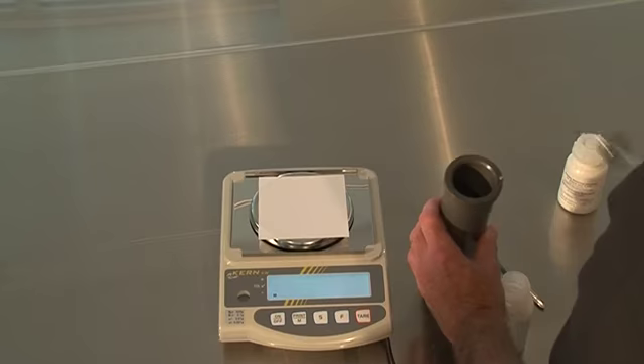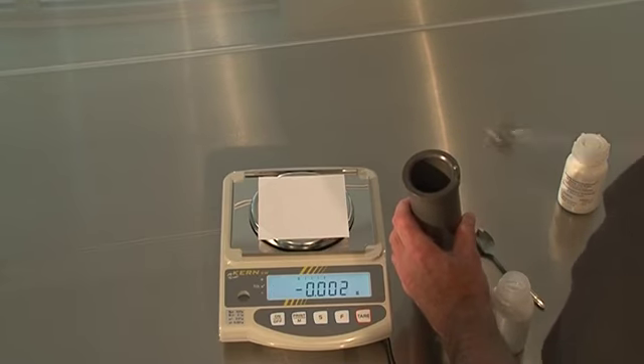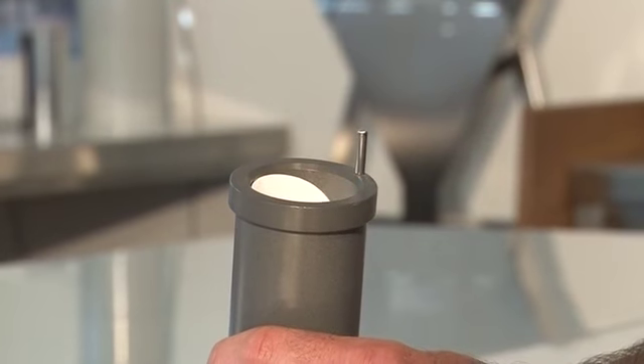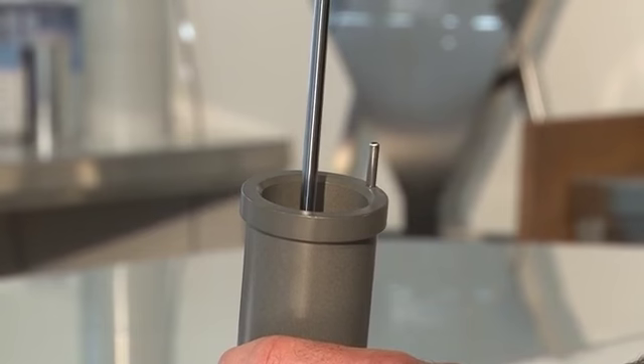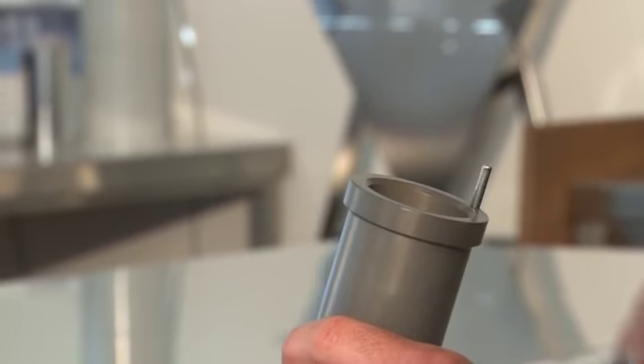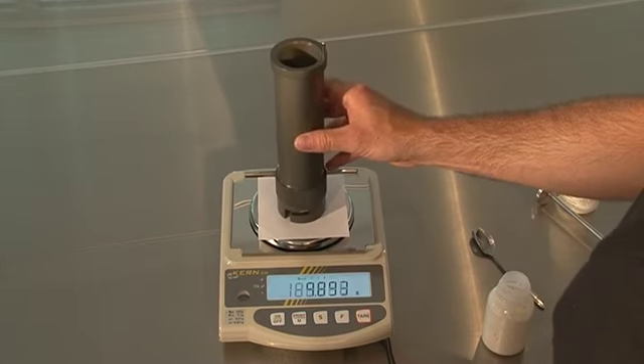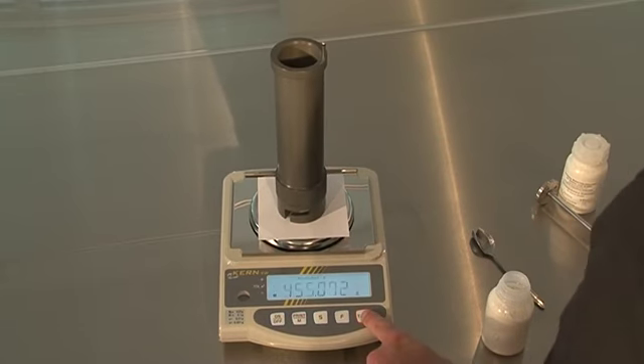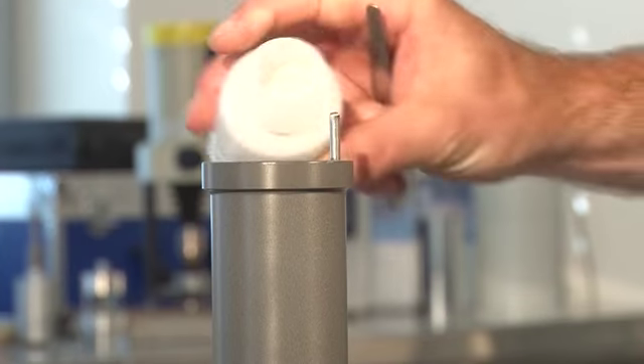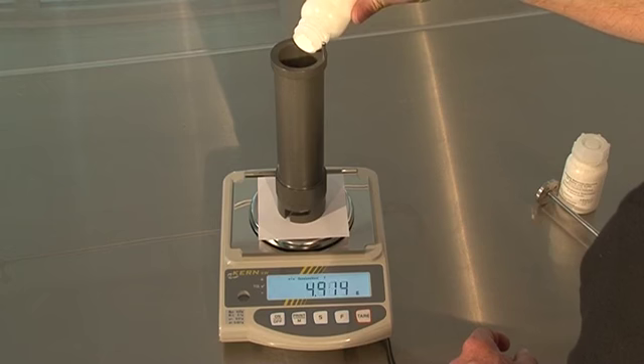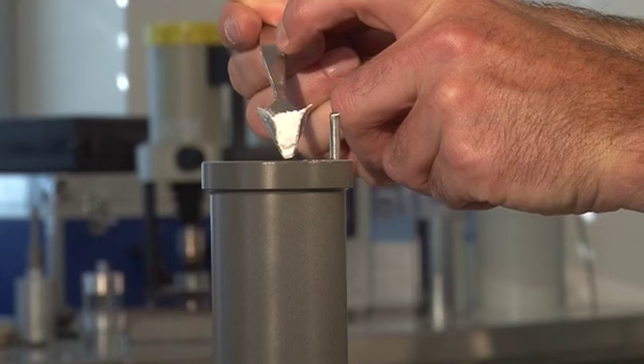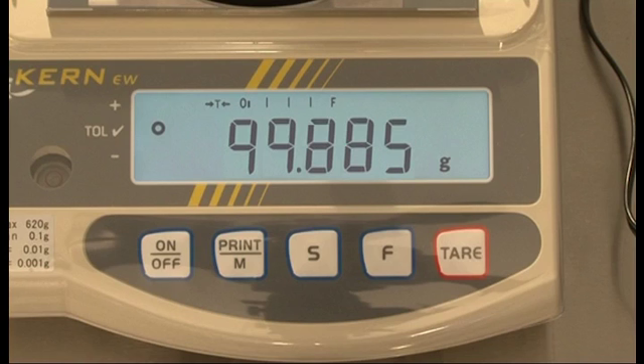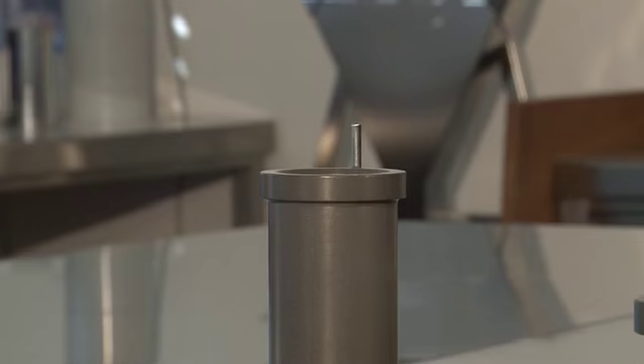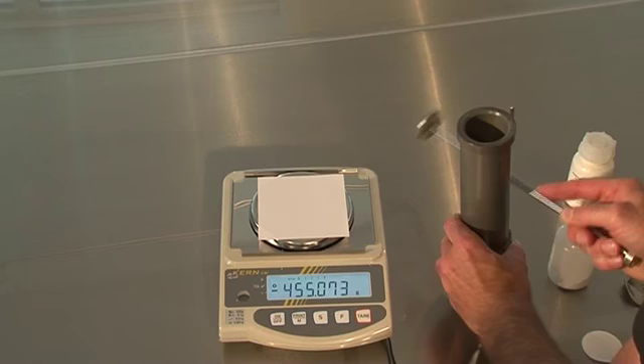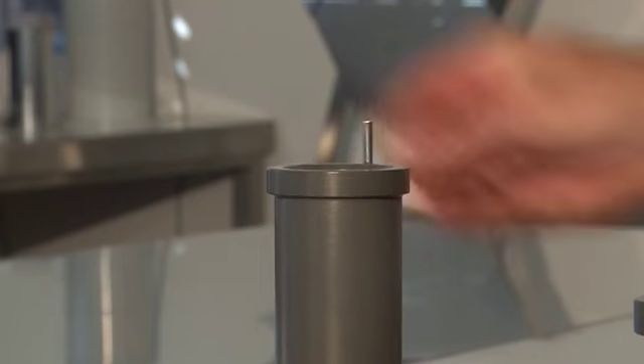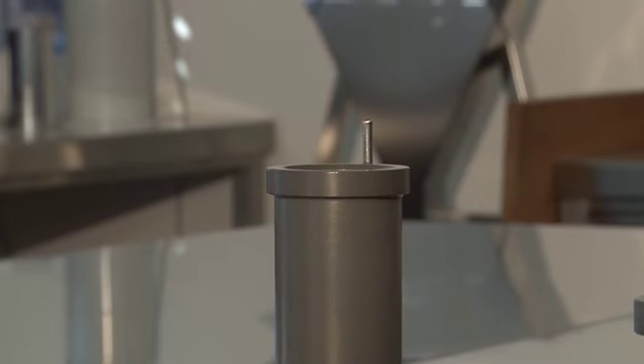Insert the perforated disc into the clean measuring cell and ensure that it lies flat on the lower edge. Place a filter paper disc on the bottom of the measuring cell, making sure it is lying flat on the bottom. Accurately weigh the calculated sample weight of the reference substance to 0.01 grams on a precision balance. Different tools can be used in the laboratory. The surface of the powder bed can be levelled by lightly tapping on the cell wall. A second filter plate is laid on the surface of the reference material with the aid of the tamper.